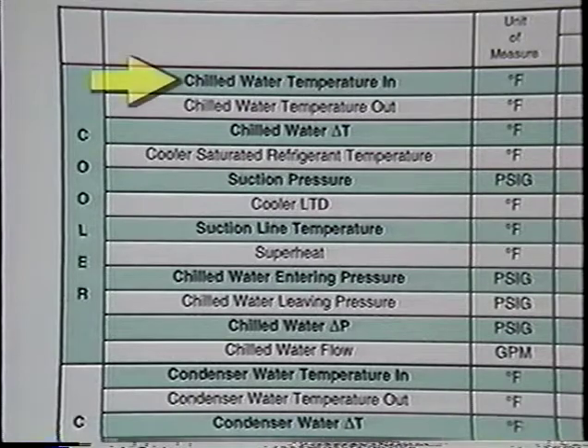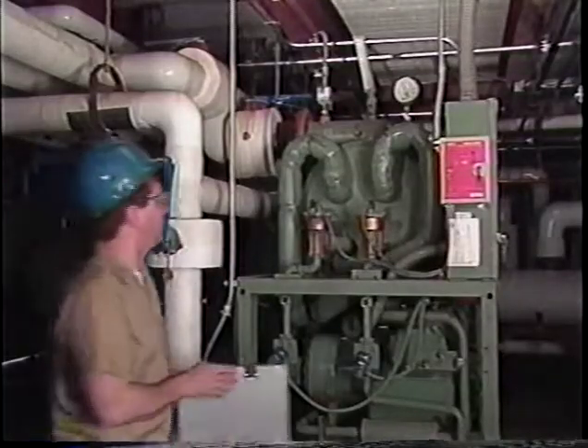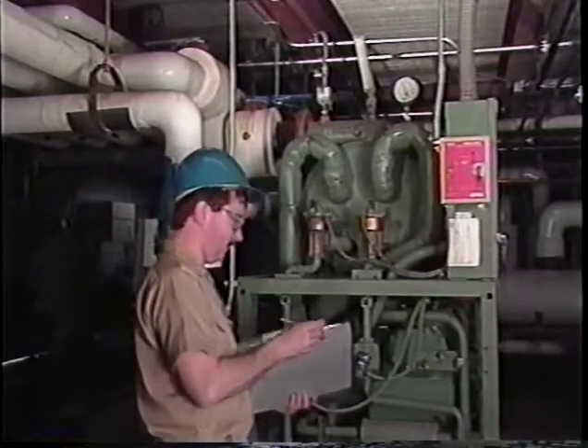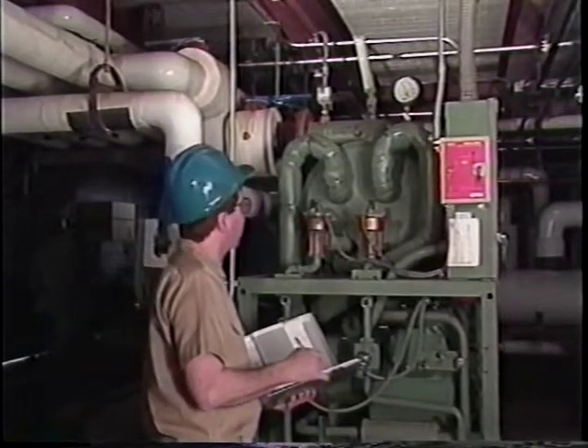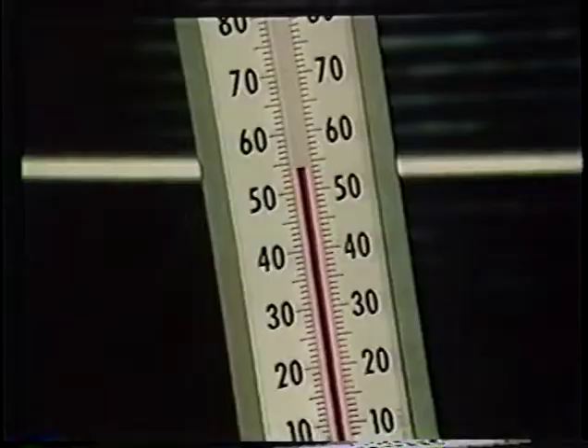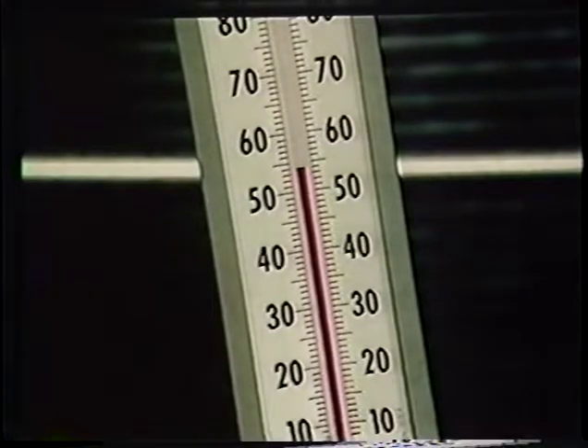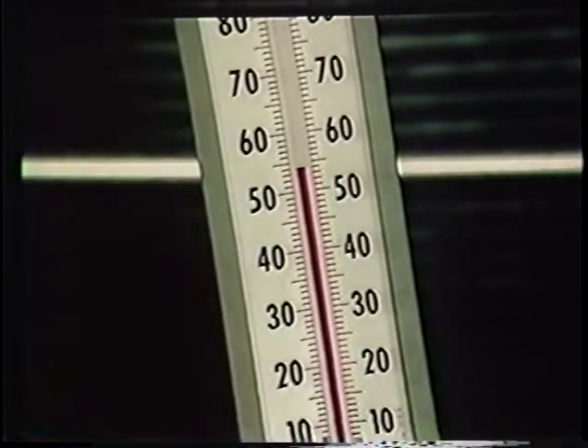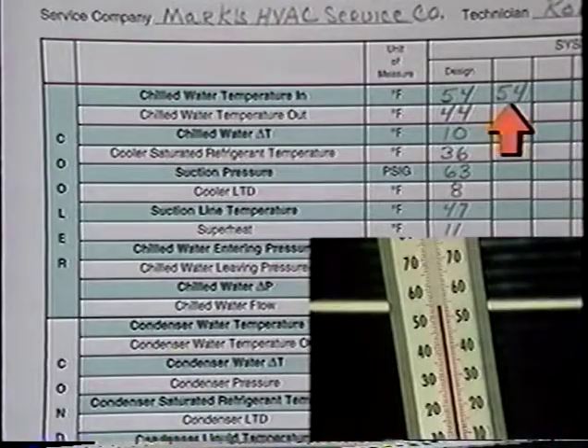Chilled water temperature entering the cooler. Prior to startup and during initial operation, this temperature will be above the design inlet temperature. Under stabilized conditions, this temperature should drop steadily until it reaches about 54 degrees Fahrenheit. Read and record the entering water temperature to the cooler.